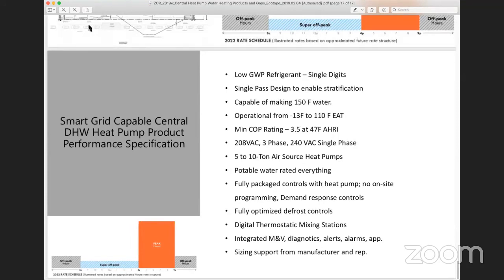We've done some calcs at 190, and that does save quite a bit of storage, but you take a hit on COP making the hotter water. It should be operational from -13 to 110 degrees outside. Minimum COP should be around 3.5 at 47. 5 to 10 ton size. Power requirements: typically in multifamily buildings, we're either 208 3-phase or 240 single, but 208 3-phase is most common. Everything's potable rated. Fully packaged controls.